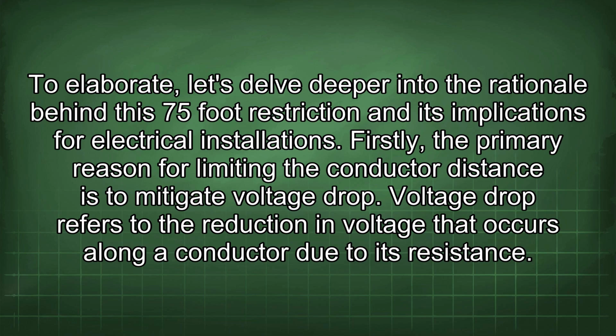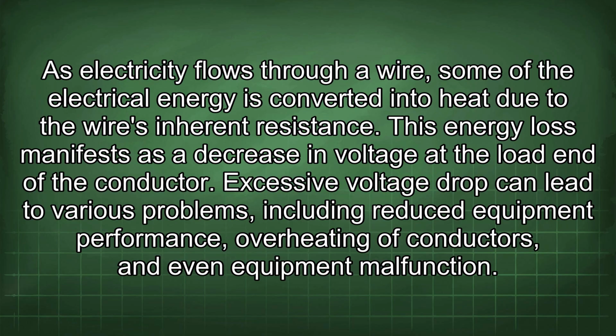To elaborate, let's delve deeper into the rationale behind this 75-foot restriction and its implications for electrical installations. Firstly, the primary reason for limiting the conductor distance is to mitigate voltage drop. Voltage drop refers to the reduction in voltage that occurs along a conductor due to its resistance. As electricity flows through a wire, some of the electrical energy is converted into heat due to the wire's inherent resistance. This energy loss manifests as a decrease in voltage at the load end of the conductor. Excessive voltage drop can lead to various problems, including reduced equipment performance, overheating of conductors, and even equipment malfunction.